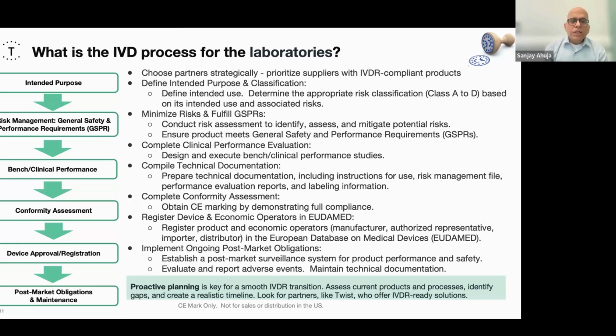And then there is a conformity assessment for ISO 13485 that the notified bodies have to perform, in terms of whether our quality management system conforms to the ISO 13485 standard. Once we have that assessment completed, in addition to the bench testing and the clinical performance testing, and also the clinical evaluation report, which has the appropriate clinical summaries, you obtain the device approval and registration, and you start marketing the products in the field. And then there is a feedback mechanism where you have post-market obligations and maintenance.